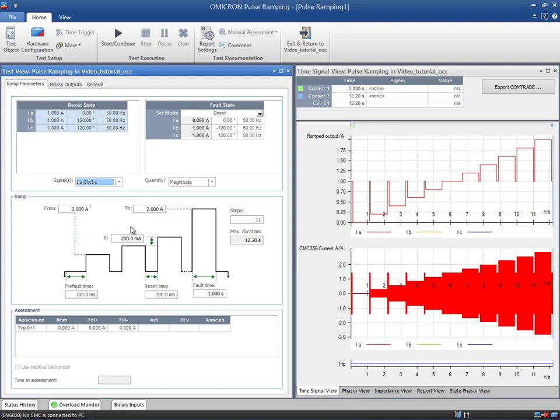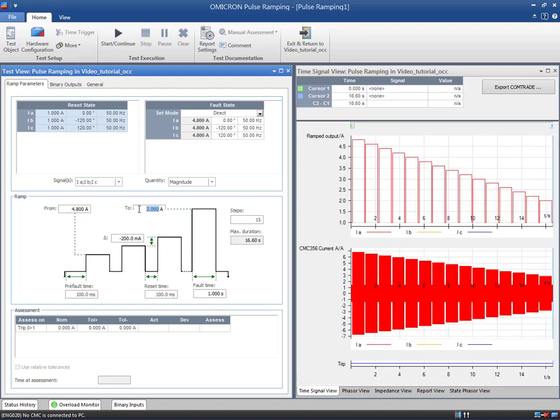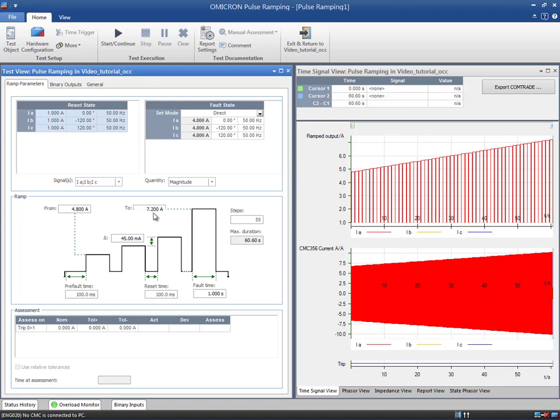Then, the start value will be 4.8 Amps. The end value, 7.2 Amps. And Delta, 45 Milliamps. The rest of the parameters to be output during the pulses can be defined in the fault state table. Balanced angles and a frequency of 50 Hz are set.